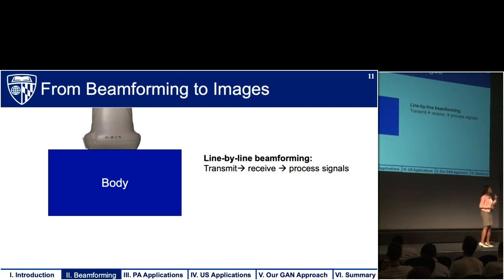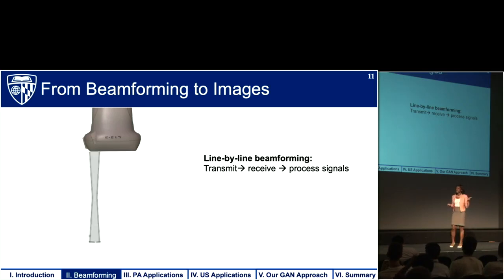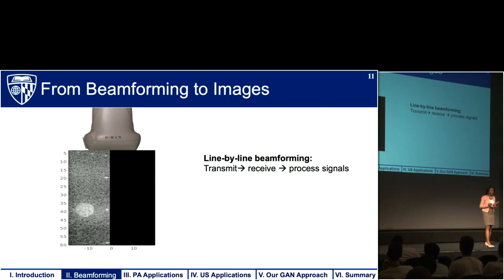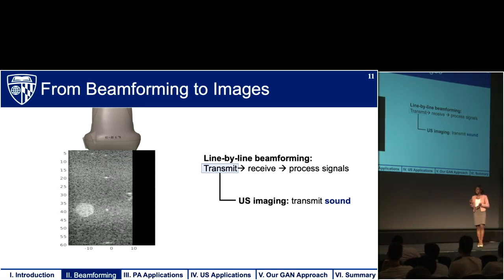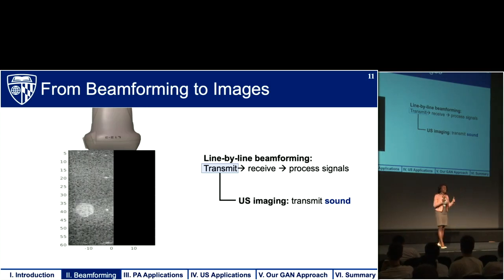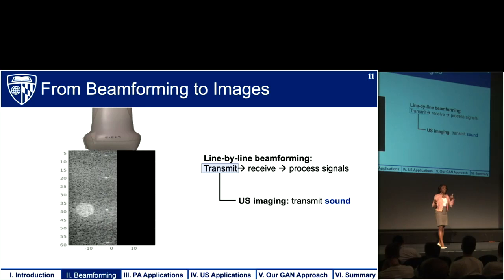To go from beamforming to images, we use a mathematical formulation to focus the beam at different locations along the aperture, receive the echoes, and build up an image line by line. We transmit sound and receive sound, performing the same concept to focus the energy of the received signals on both the receiving and transmit ends — so we have both transmit and receive beamforming.